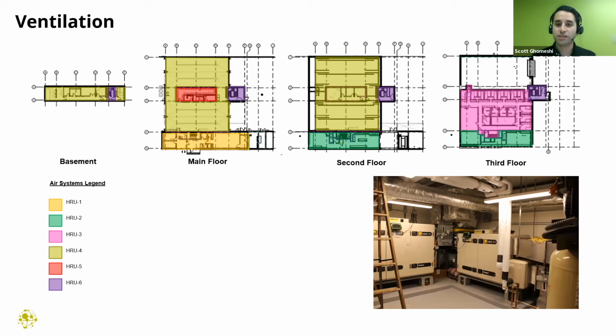This project has been in the making for quite some time. When we started, Swegon was just about to enter our market, and the only other passive house certified component anywhere near this level of performance were the Zehnder Comfo Air 350s, which weren't really tasked with operating at the airflows we needed for a Firehall. We were lucky Zehnder had brought in these units, so we designed around that. The one disadvantage was that the react dampers weren't quite there, so we zoned different spaces and occupancies based on their usage and occupancy patterns, so whole zones could ramp up and down based on the peaks and ebbs and flows of occupancy throughout the space.